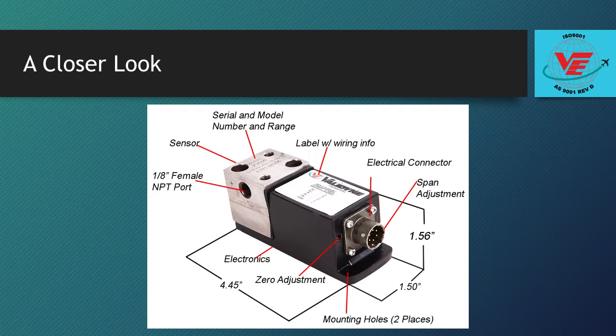Zero and span controls used for adjusting the output signal are found on the rear of the electronics housing next to the connector shell. They are marked with a Z for zero and an S for span. Note there are gaskets at the sensor and connector surfaces to make this a weatherproof enclosure.